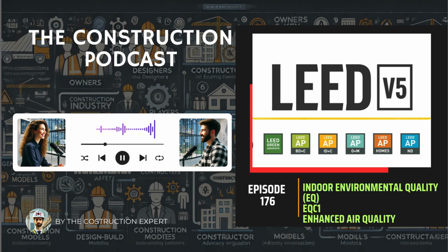Okay, let me try to quickly summarize option 2 then. We are talking about deliberately engineering a specific chemical environment inside the building. We're targeting PM 2.5 down to 10 micrograms per cubic meter, which demands extreme filtration. We're targeting formaldehyde down to 20 micrograms per cubic meter, requiring meticulous low VOC material sourcing and vetting. And we're targeting ozone down to 10 parts per billion, necessitating the exclusion or isolation of ozone-generating equipment.